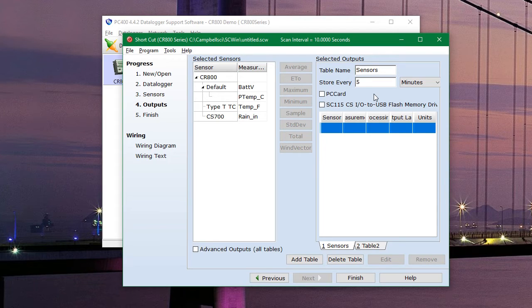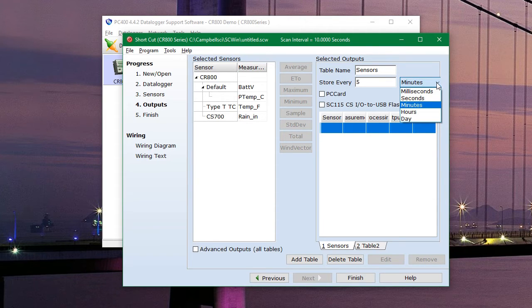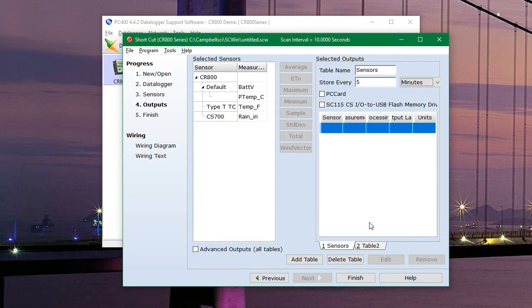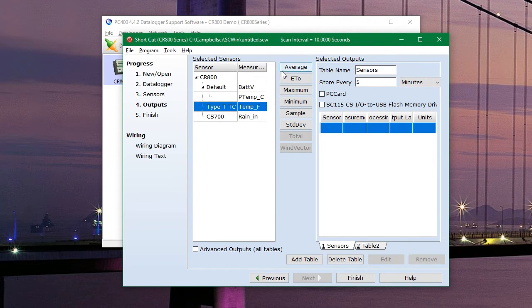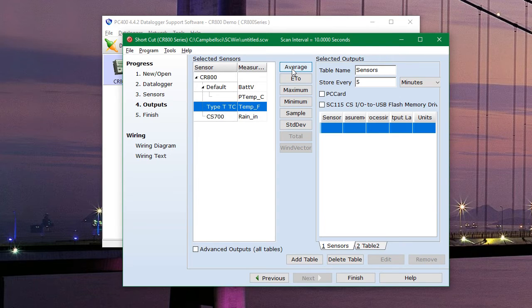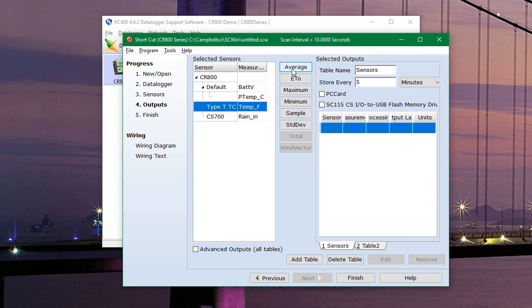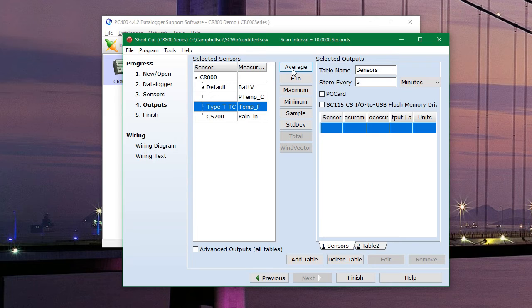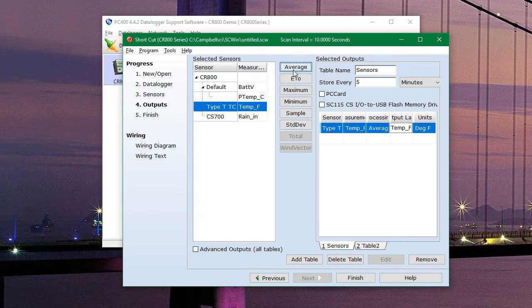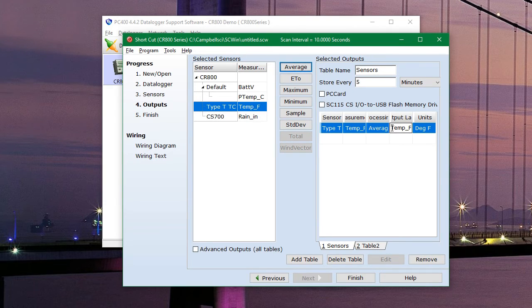And then on the left side, we have our available measurements. So we have this type T thermocouple. And in the middle are all of the different ways we have to save that data to the table. So what that means is that the data logger will read the temperature from that sensor every 10 seconds. And then after 5 minutes, it will store the average temperature over that time. So click on average. And again, we can rename that measurement to anything we want to.